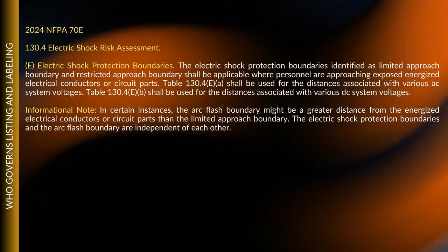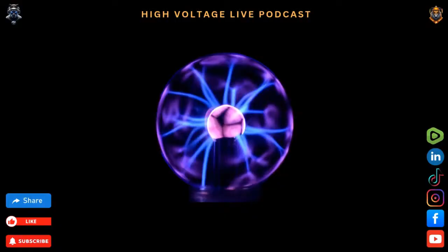The same principle applies if I'm working on that disconnect behind an AC unit. 100%. And that's why I like to bring this up for everybody to see as an example. I gave you all the tables, all the information there that shows you the difference when you get in, looking at the likelihood of occurrence. You're not inside the restricted approach boundary, and you're providing additional means of protection there in order to verify it's in the de-energized state. And then once you're going to do that thermography testing, you're outside the restricted approach boundary. Why would you need the working clearance? 100%, 100% agree.